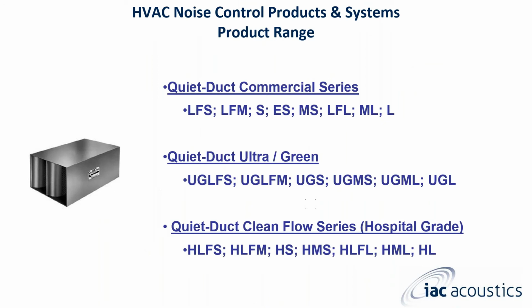You're going to see it through the Quiet Duct Commercial Series. That is basically like 70% of the bread and butter that's out there in the market today. We have our Quiet Duct Ultra Green and our Quiet Duct Clean Flow series, nicknamed our hospital grade. You see it uses the same basic nomenclature for the LFS and the UG Ultra Green LFS or the H hospital grade LFS. So in essence, these three LFS silencers will have the same baffle arrangement inside, the same open air passage and things like that as well. But with the Quiet Duct Commercial Series, it is filled with fiberglass only.